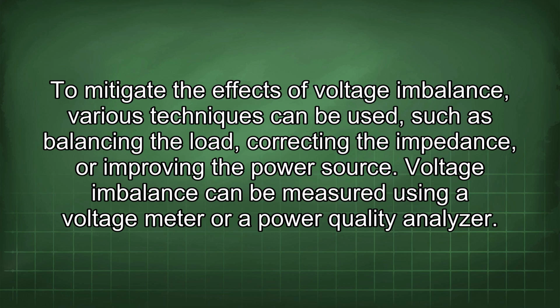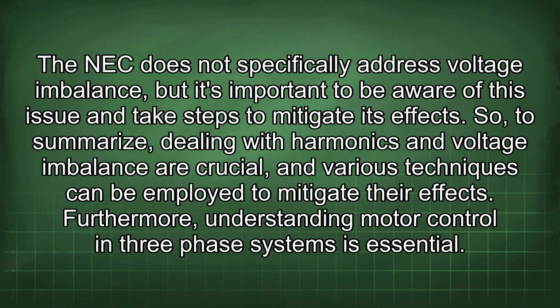Voltage imbalance can be measured using a voltage meter or a power quality analyzer. The NEC does not specifically address voltage imbalance, but it's important to be aware of this issue and take steps to mitigate its effects. So, to summarize, dealing with harmonics and voltage imbalance are crucial, and various techniques can be employed to mitigate their effects.